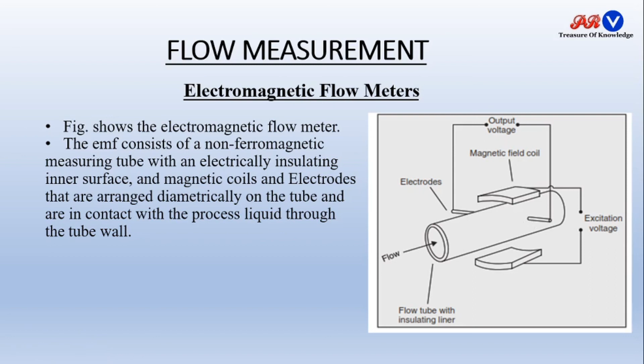The EMF meter consists of a non-ferromagnetic measuring tube. This tube is non-ferromagnetic with an electrically insulating inner surface. The magnetic coils and electrodes are arranged diametrically on the tube, and the electrodes are in contact with the process liquid through the tube. So, the two electrodes are inside the pipe.